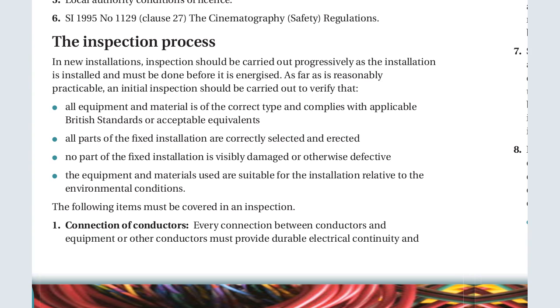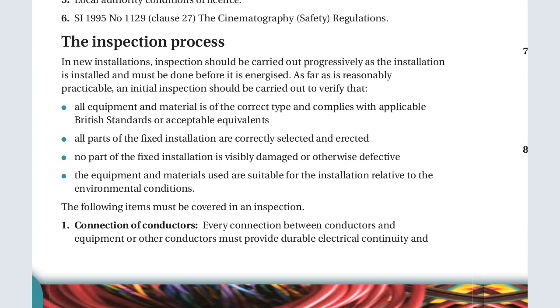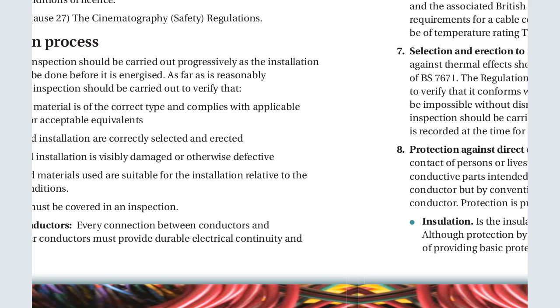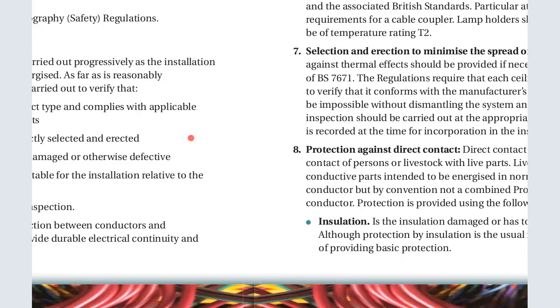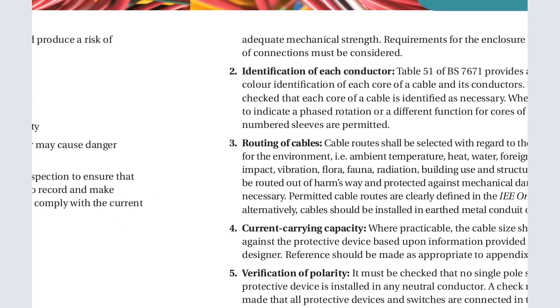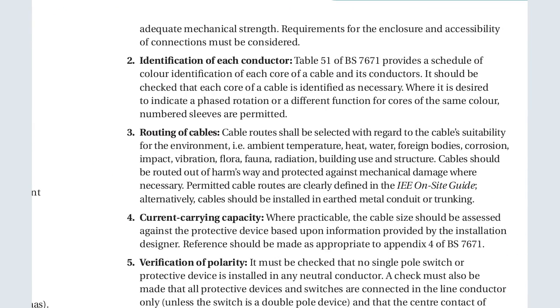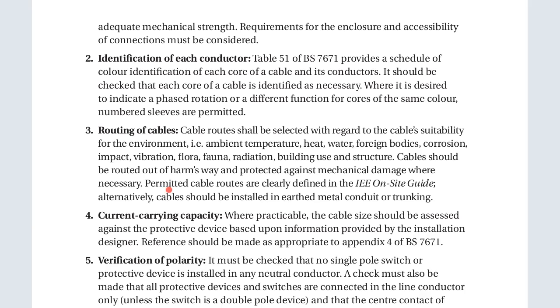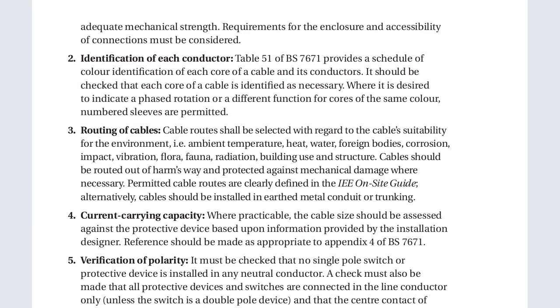The following items must be covered in the inspection. Number one is the connection of conductors. That is, every connection between conductor and equipment and other conductors must provide durable electrical continuity, meaning there has to be continuity, and also adequate mechanical strength. That is, the requirements of the enclosure, the accessibility and the connection must be considered. Another one is the identification of each conductor.